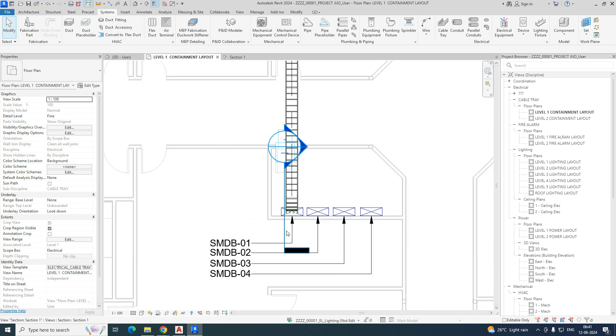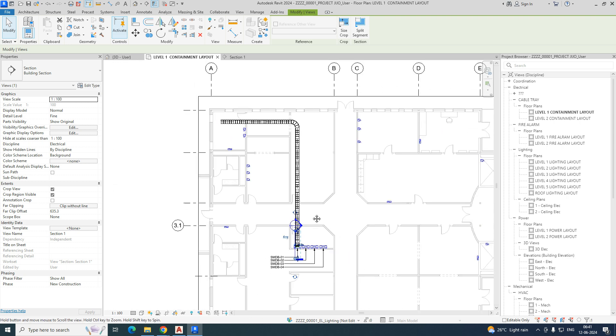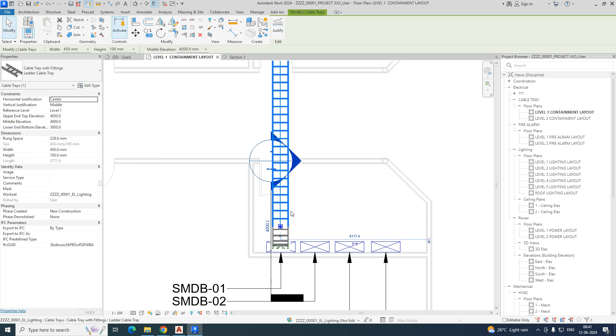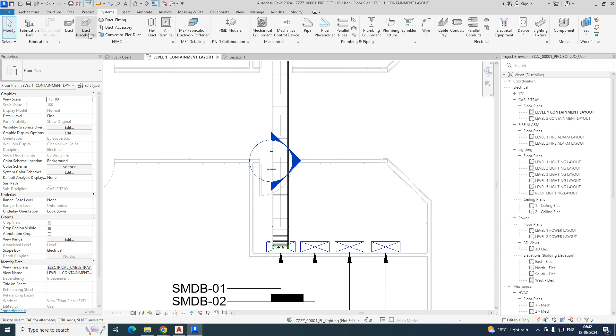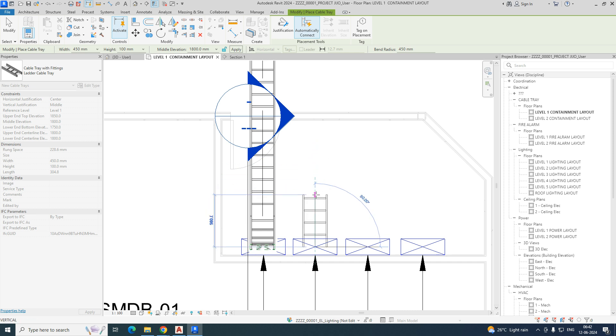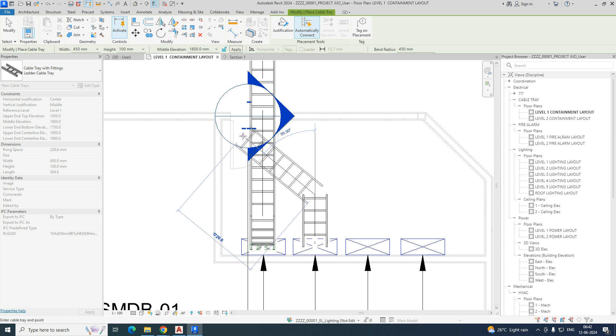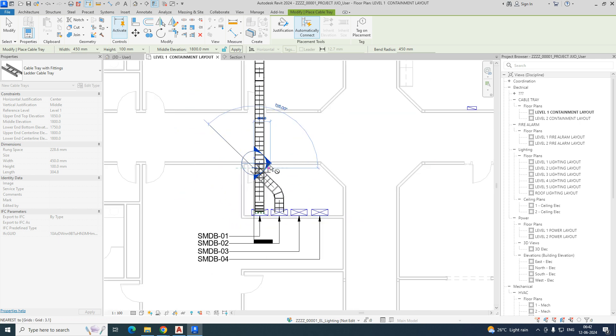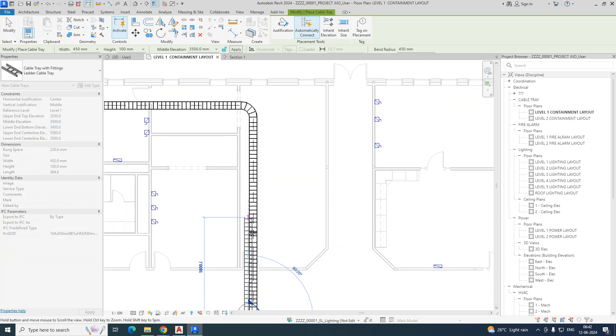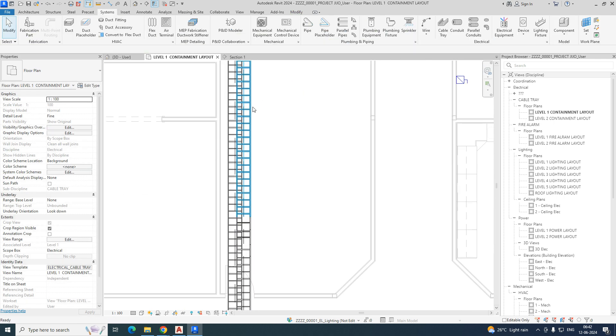Like that, we can make cable ladders at different layers. For example, I need to make another cable tray below this one. I start one cable tray from here and it will run through the same route. Go to System, Cable Tray — same cable tray. I'm drawing it at a 45-degree angle up to here, keeping it at a height of 3500.